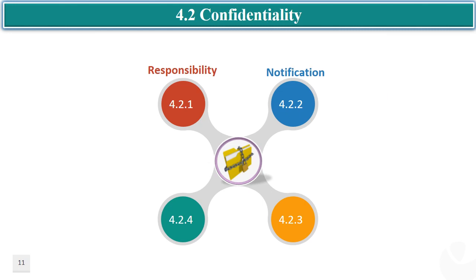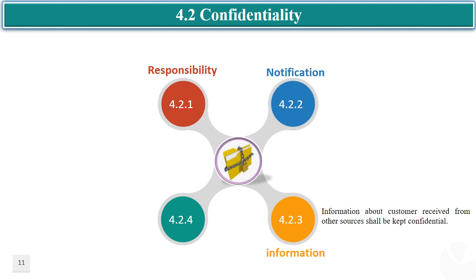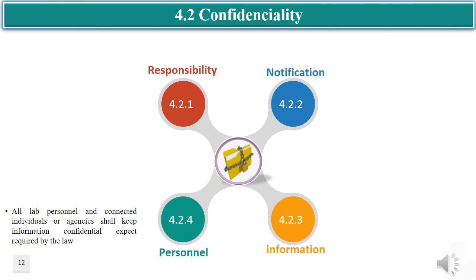Whenever the laboratory obtains information about customers from other sources, that information shall be kept confidential. The sources of the information shall not be shared with customers, unless agreed with the information provider. Sub-clause 4.2.4 requires that all personnel connected with or involved in laboratory operations — such as committee members, contractors, personnel of external bodies, or individuals acting on behalf of the laboratory — shall also maintain confidentiality.